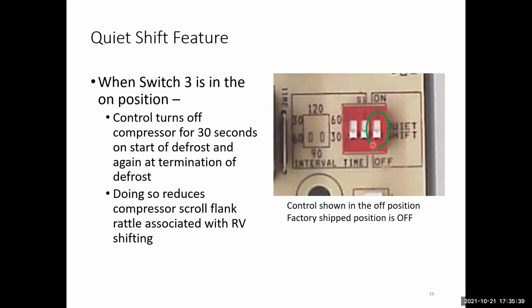Again, just showing you the different positions of it. This feature does not address or mitigate improper airflow, improper system charge, or installation where the outdoor unit is subject to excessive moisture and water from roof runoff, deck runoff, or any other structure causing water to be directed towards the unit. A compressor that operates for some period of time with incorrect refrigerant or commissioned incorrectly may become noisy, and this feature cannot address that noise issue.